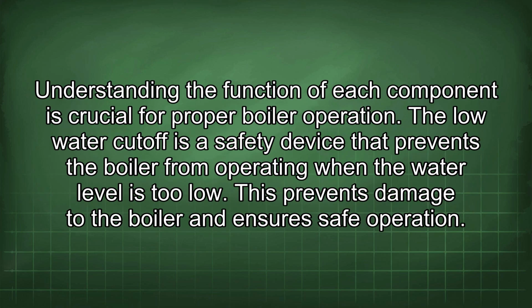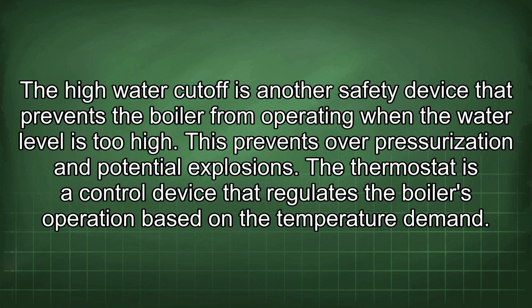Understanding the function of each component is crucial for proper boiler operation. The low water cutoff is a safety device that prevents the boiler from operating when the water level is too low. This prevents damage to the boiler and ensures safe operation. The high water cutoff is another safety device that prevents the boiler from operating when the water level is too high. This prevents overpressurization and potential explosions.